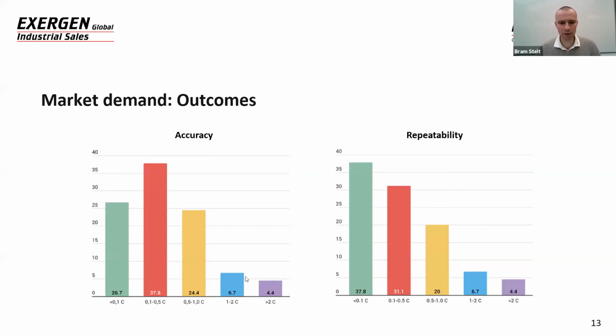Repeatability shows kind of a similar trend, where the red bar, over 30%, wants to have a repeatability between 0.1 and 0.5 degrees C, and the green bar, almost 40% of all respondents wants to have a repeatability of 1/10 of a degree or better. That's quite challenging to achieve. That's not easy, but we're always up for a challenge.